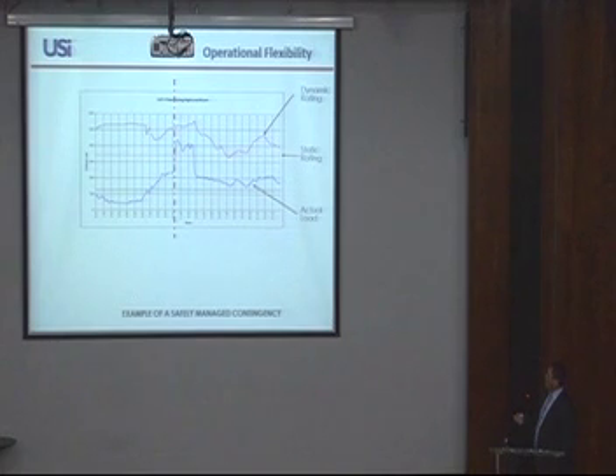It was much higher. So although he was at the thermal or the static rating, the conductor temperature was not 75 degrees. The 75 would have been with his dynamic line rating, so he could just wait and see how the current goes up without violating any clearance requirements. In that case, it took 3 hours to solve a problem, and the current went down again. And the operator, let's say, solved the problem just by doing nothing.